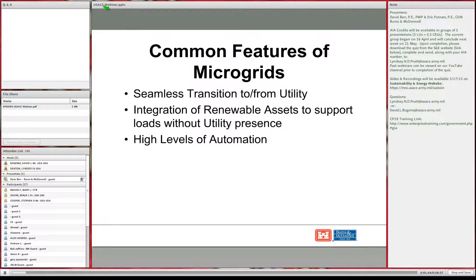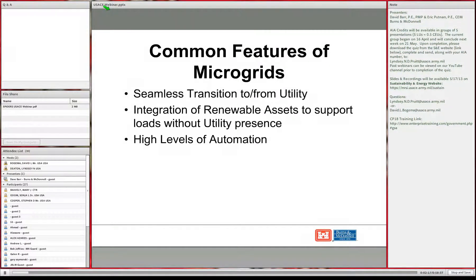In a building generator system, when you lose power unexpectedly, the generator comes on but there's a small delay, and typically when power comes back there's another delay as the transfer switch switches back to utility—unless it's a closed transition type. In a microgrid, ideally you want to avoid those blips, at least other than from an unanticipated utility outage.